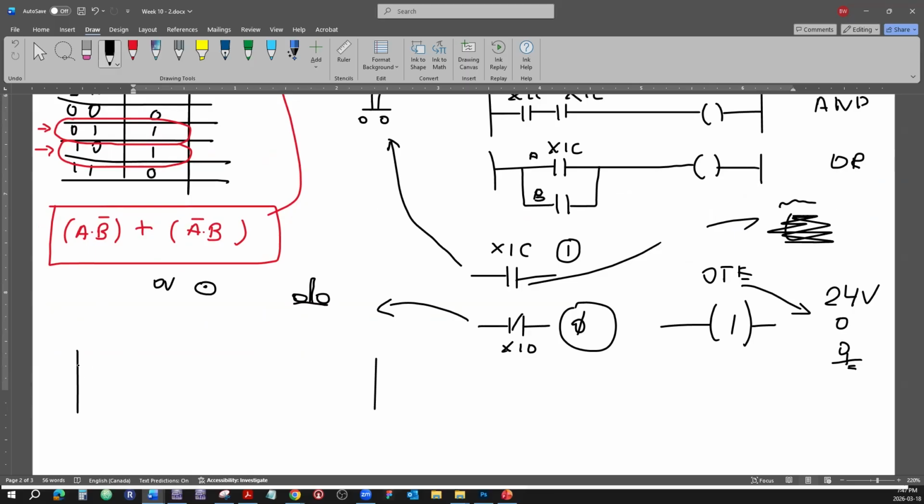So in the rung, we have one instruction. This is going to be input A, and input B. But because we have that not thing, this is examine if closed here, examine if open here, we apply this instruction. And then we're going to bring it to the output energize, the OTE instruction.